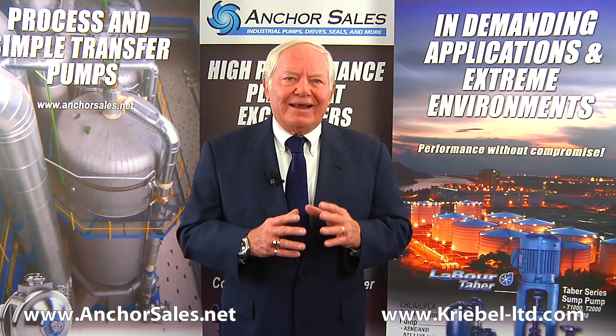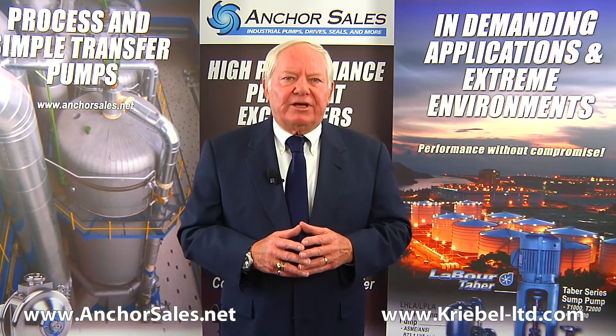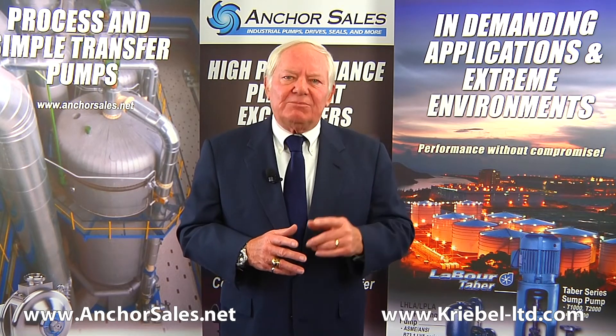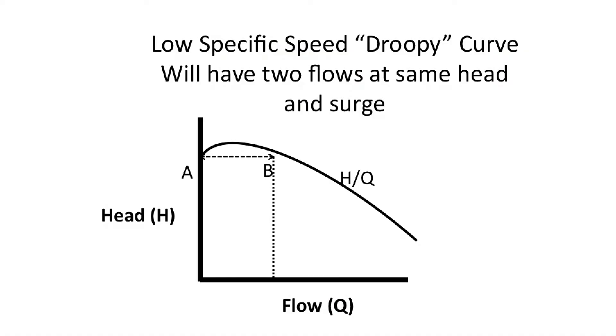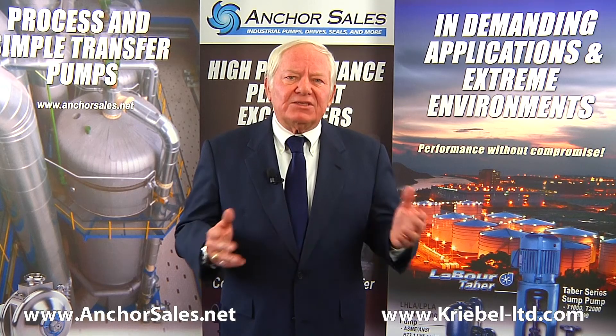But operation at low flows can shorten life. Some lower specific speed pumps have a droop at low flows, which will cause surging from point A to point B. Therefore, the pump minimum flow should be set above point B. Conversely, some high specific speed pumps have high rise to shutoff, and the downstream working pressure may limit the minimum flow.